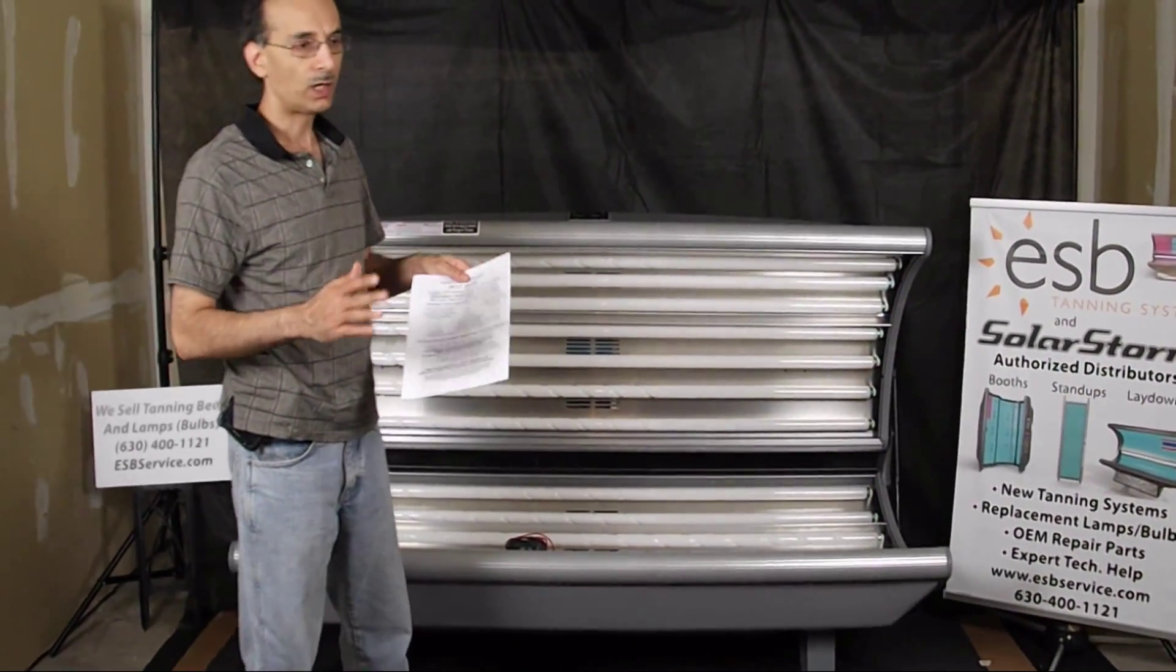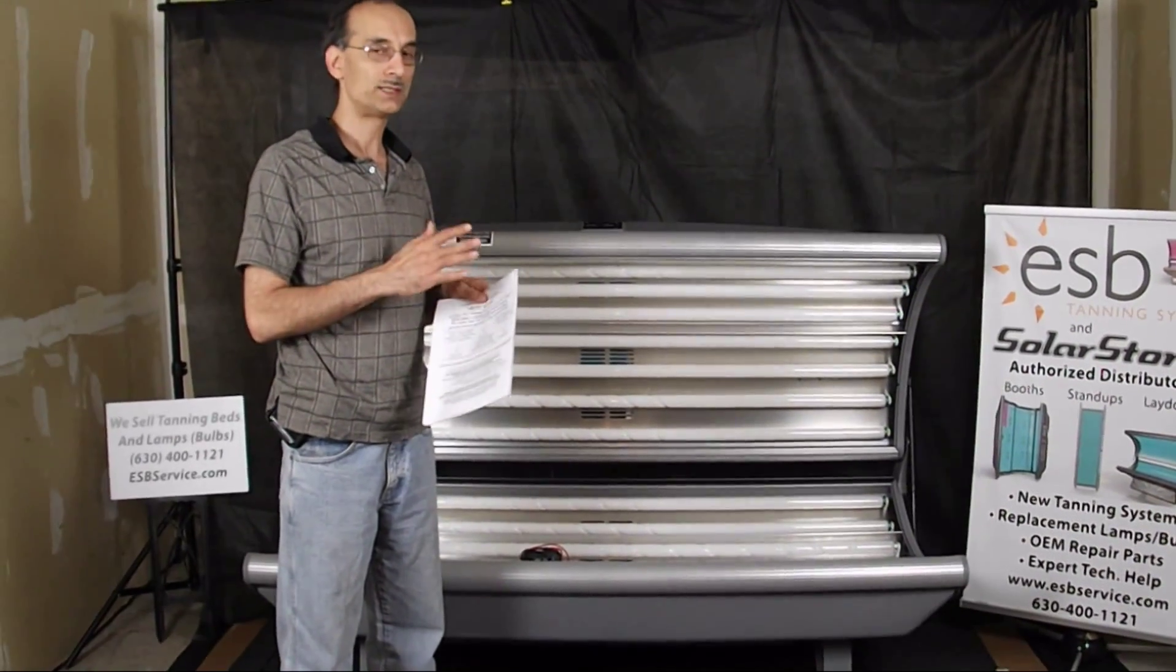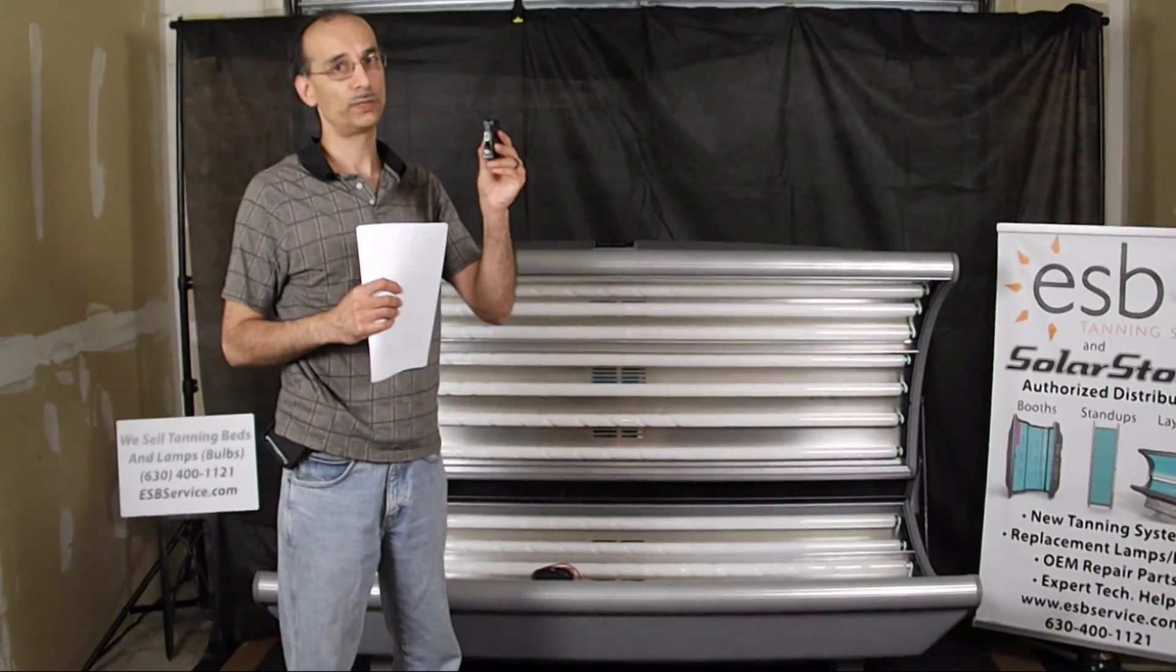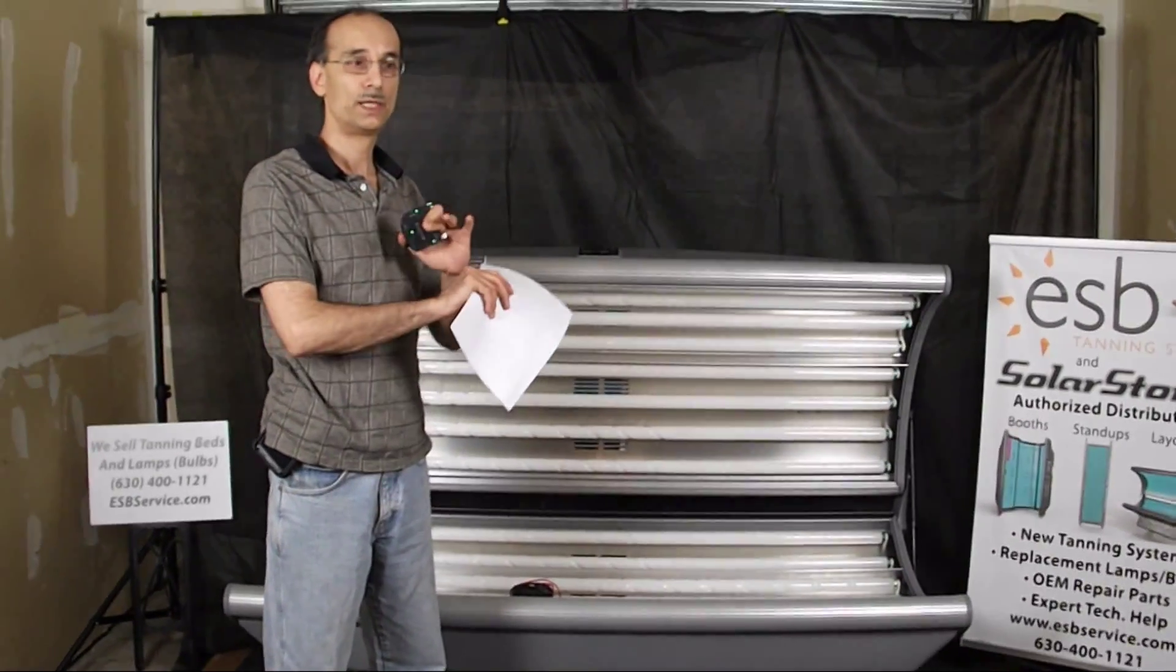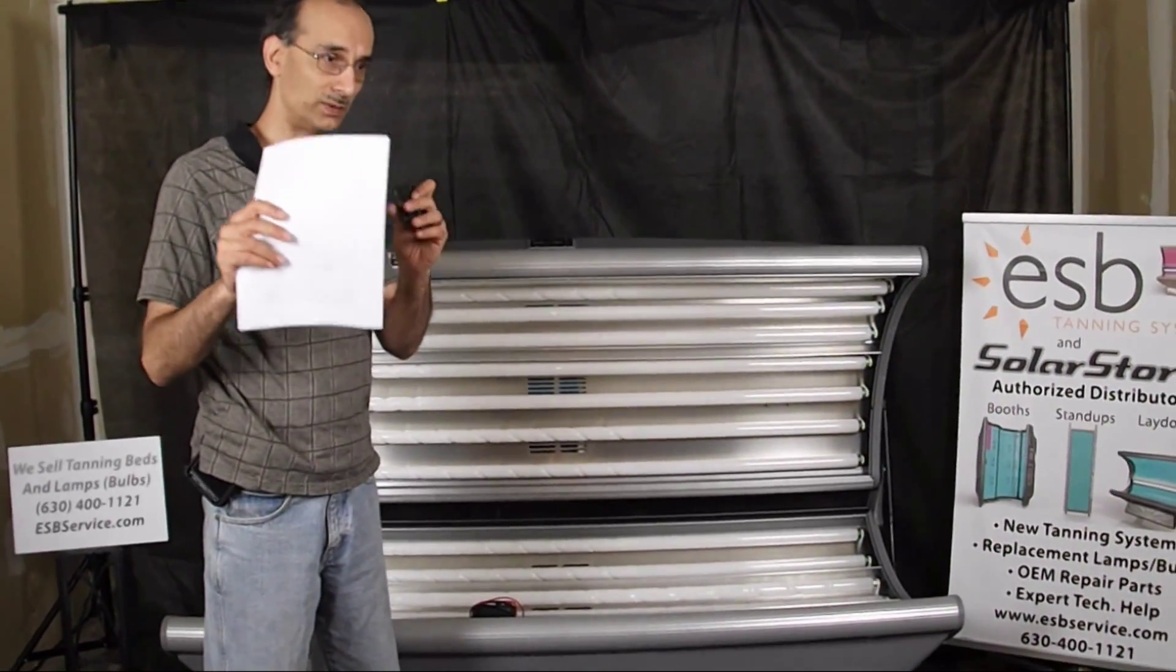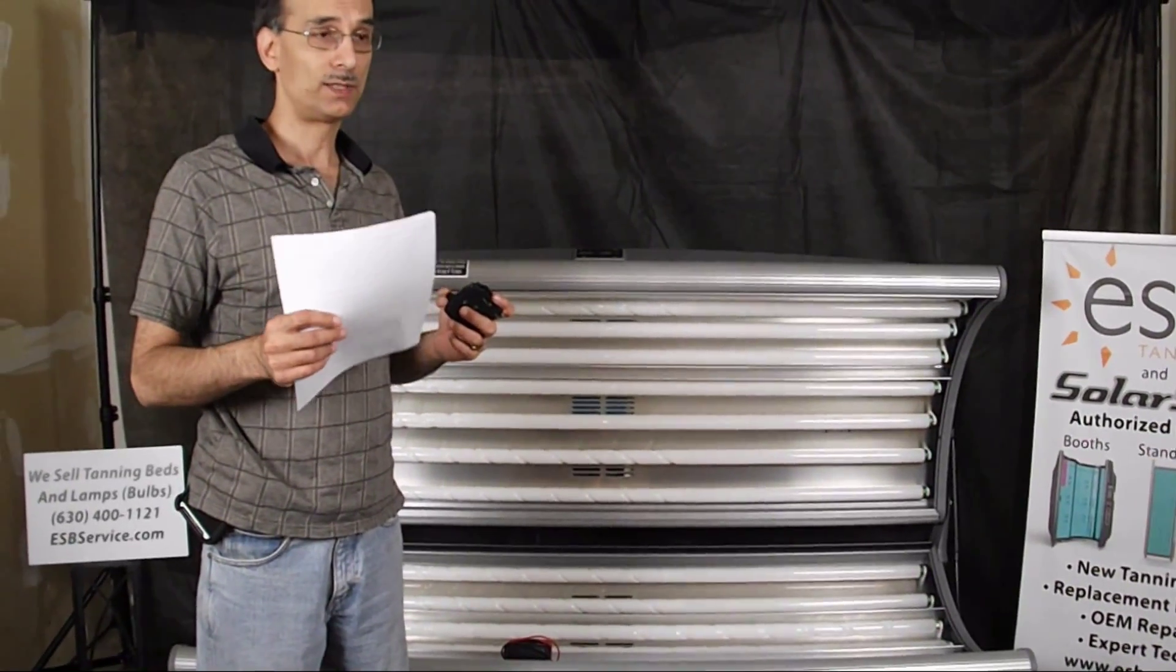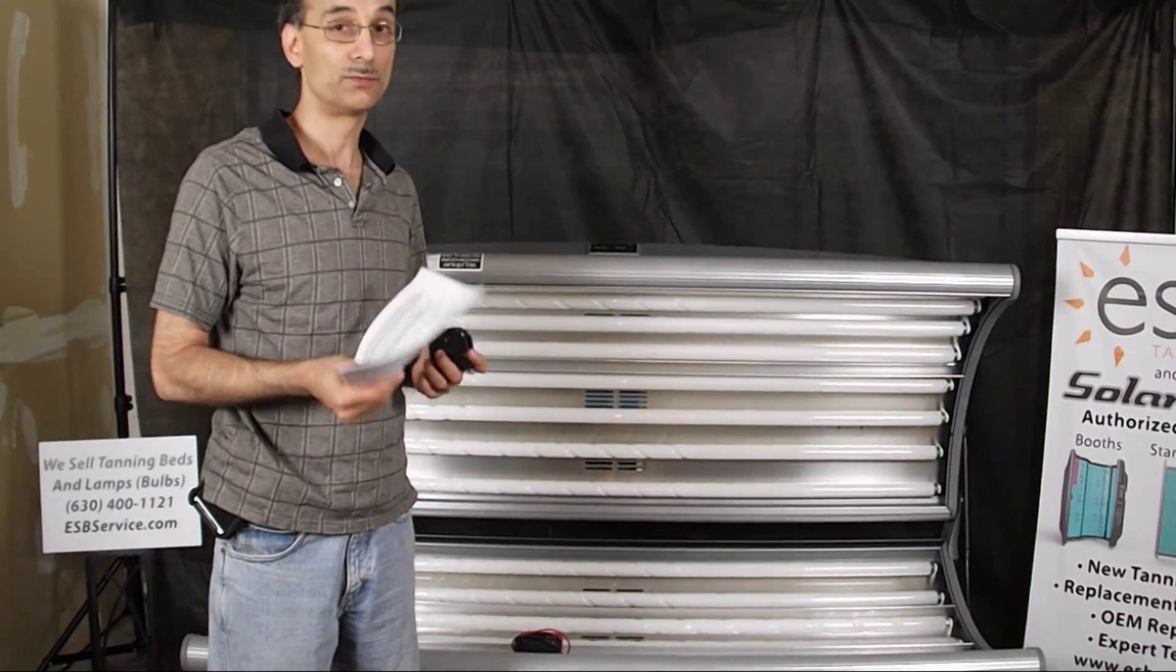Now, regardless of the model of tanning bed you have, they all need to be on a dedicated circuit breaker. That means that in your breaker box, there's one circuit breaker that goes to the receptacle that the bed is plugged into and nowhere else, no other branches or splits. It's simply dedicated to that outlet and it would also need to have the amperage capacity that's rated for the bed.